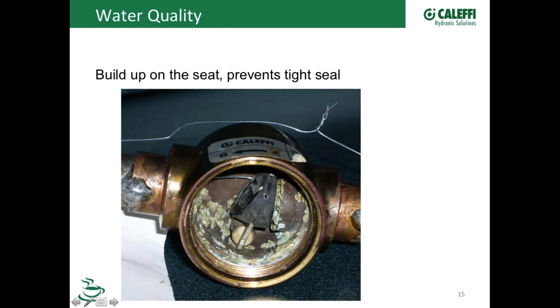But the nice thing about this valve, being a Caleffi, you can see that the bottom can be removed from this valve on all of our Z1 valves, and you can get in there and actually replace this whole assembly here if for some reason there was a nick or a gouge in it. But you could certainly open that with your fingers and get in there with maybe some scratch cloth or something like that and clean that off and put that valve back in service.